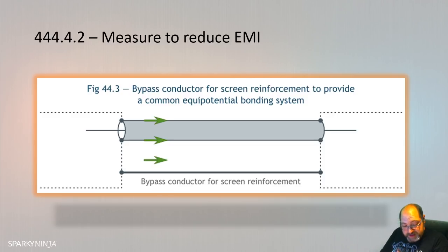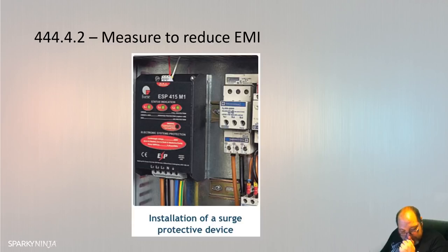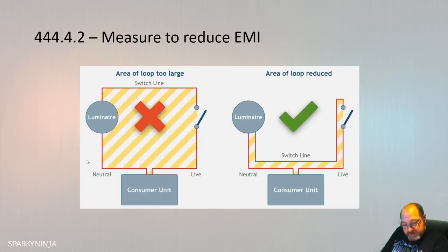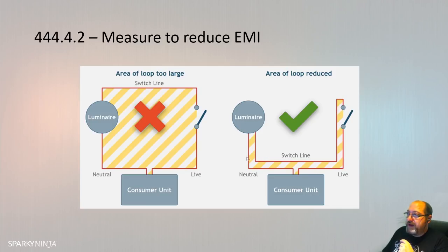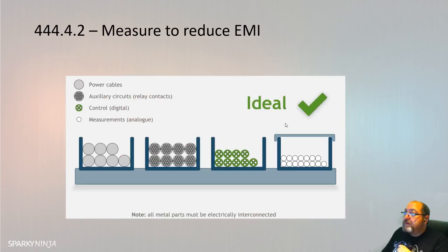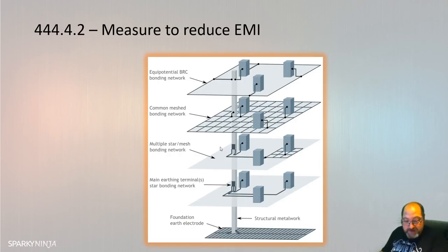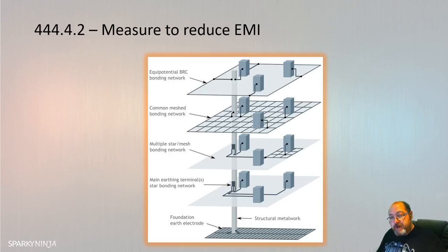Further measures include: the use of a surge protective device (SPD); installation of power cables close together to minimize cable loop areas; separation of power and signal cables into their own wiring systems; and the installation of an equipotential bonding network. The equipotential bonding network is covered in Annex A444.